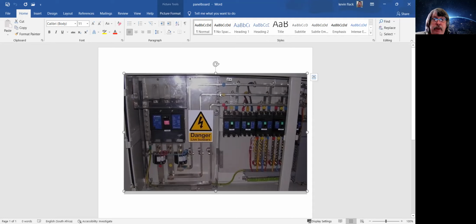So from a critique point of view, just a quick recap on this. Busbars, and that should have been tested. If you haven't tested them, you haven't got a type tested panel. By law and strictly speaking, anything above 10 kA should in fact be a type tested panel. Any extension on a system like that should be done in terms of that same thing, not just an add-on of any panel. Interface barriers, very, very, very, and I can't say too many, very important to be fitted, and fitted soundly up to the back metal plates.